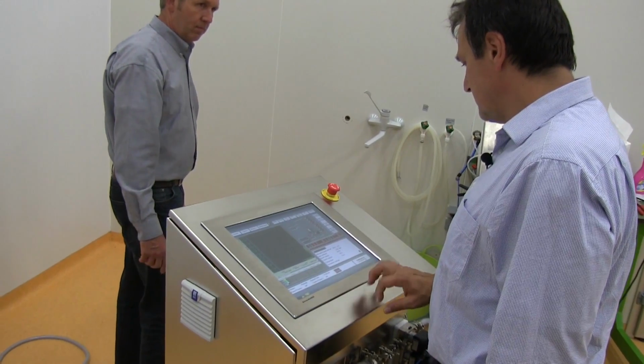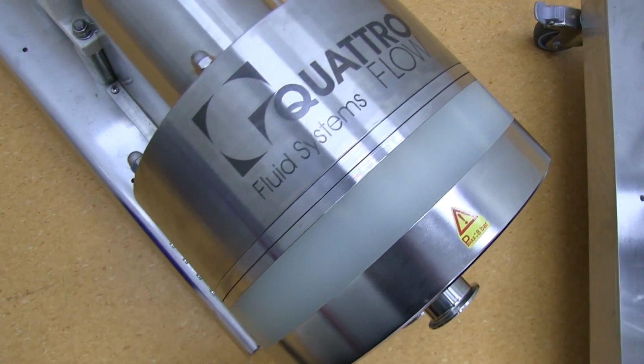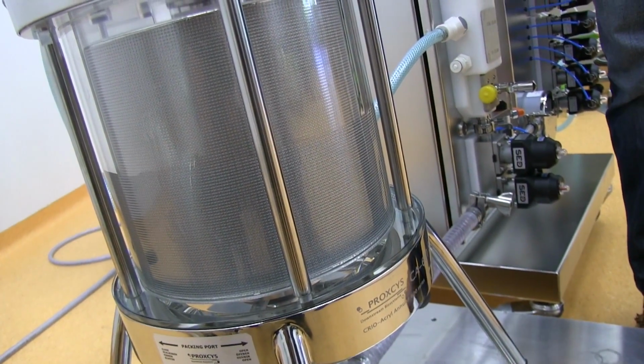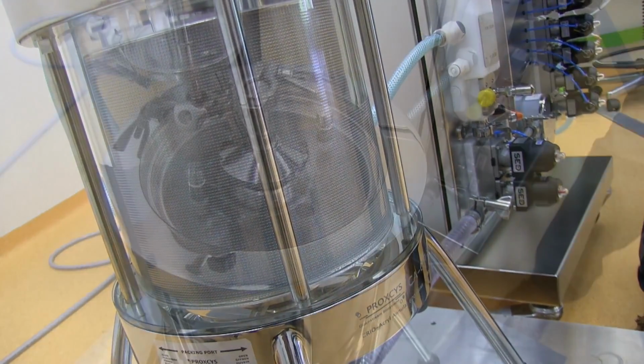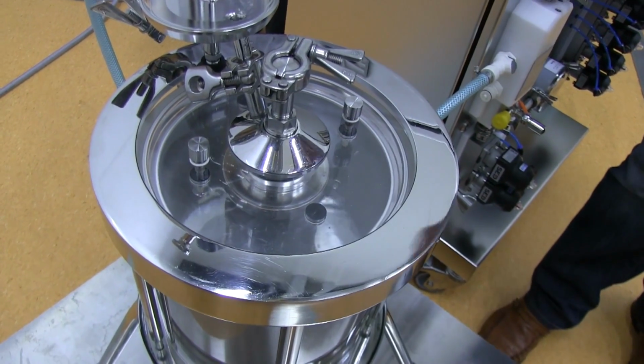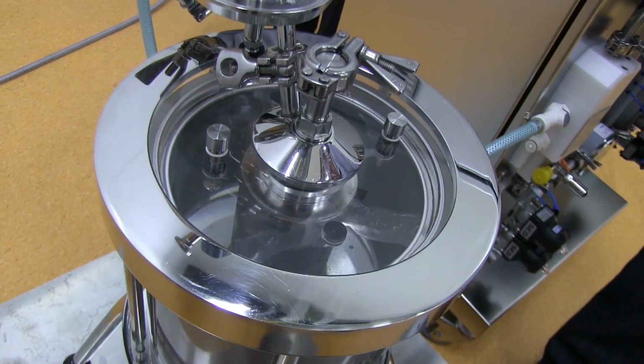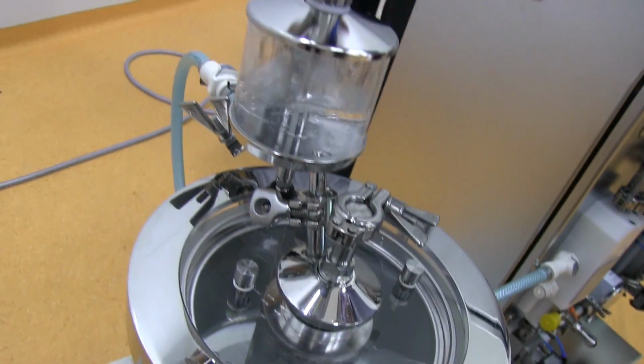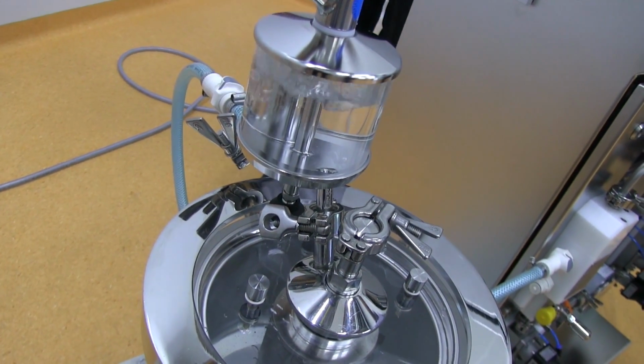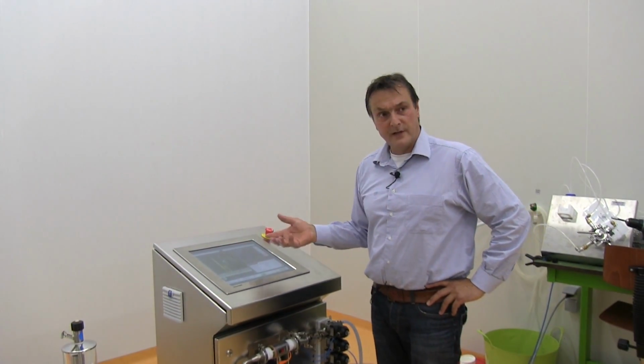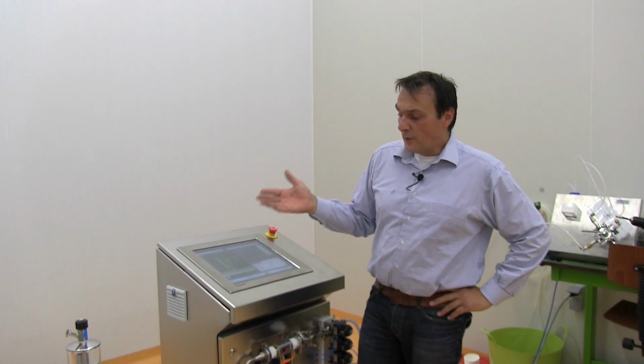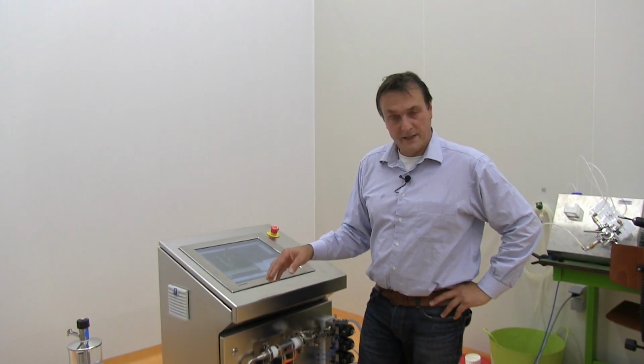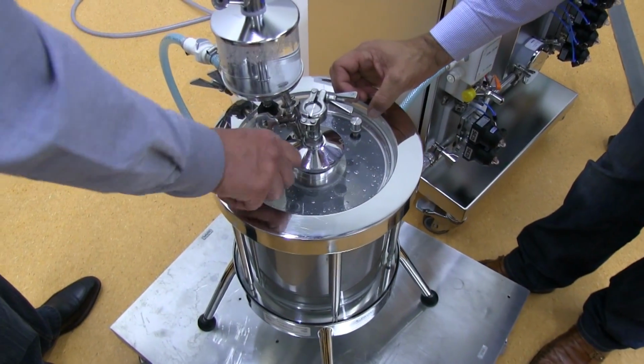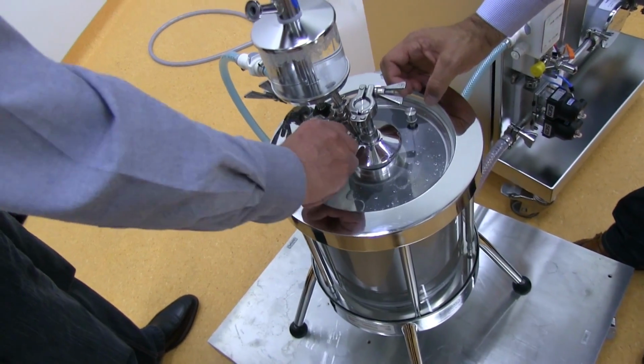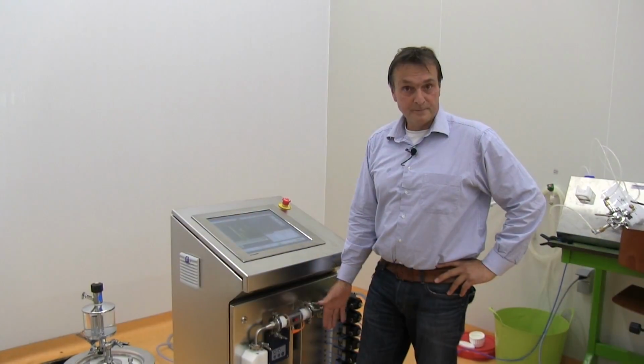What I'll show you here is how to pack a radial flow column using the pack and run system, equipped with a Quattroflow pump. The Quattroflow pump has a large turndown ratio, which is very good for this application since packing the radial flow columns needs a bit higher flow, at the upper range of the pump. The evaluation, the HETP assessment, the quality assessment of the packed bed, is done with a lower flow rate, also supplied by the same pump.